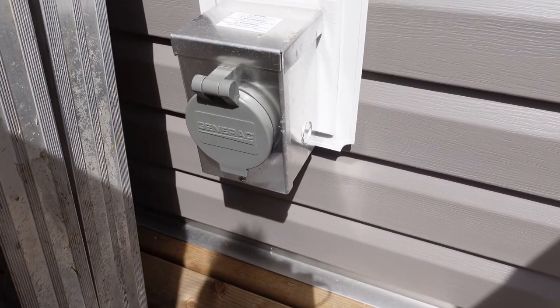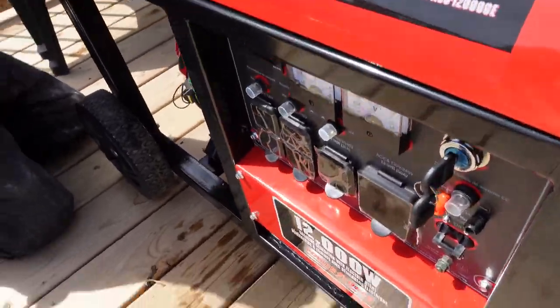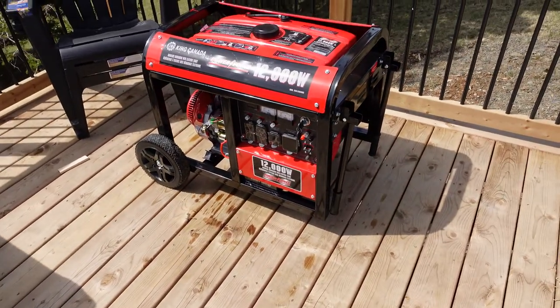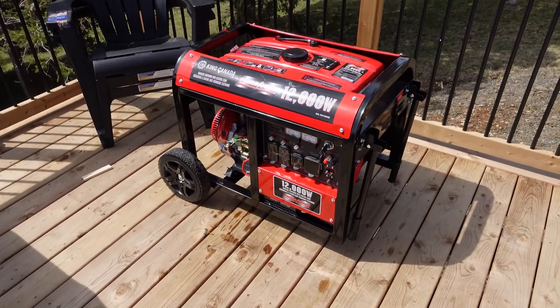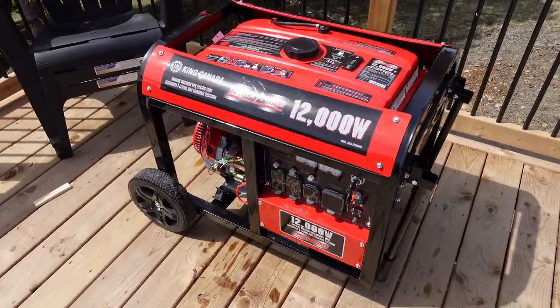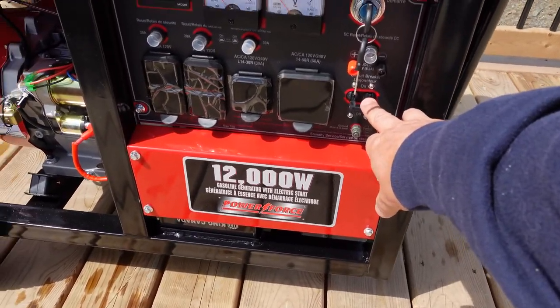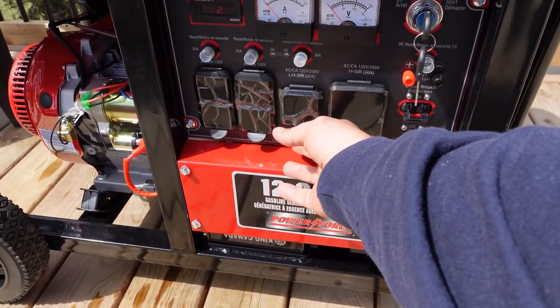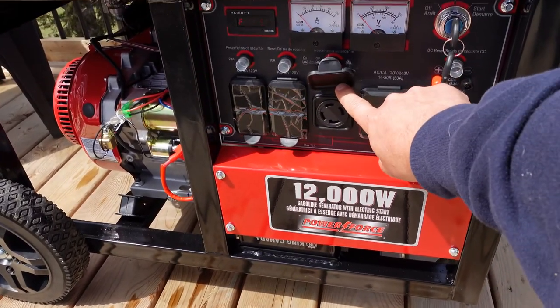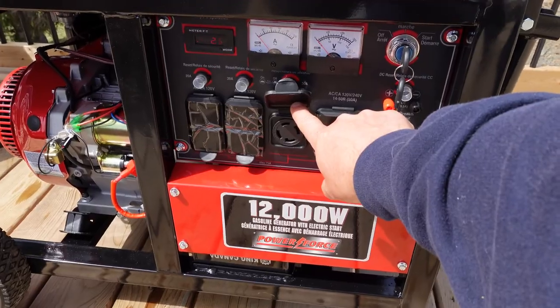Now we're going to do a startup and get the generator going. The first thing you're going to do is get your generator running. All models are a little different — some have a choke, some have electric start. On the side of the generator when you turn it on, you're going to want the breaker in the off position. This is the L14-30R receptacle that you're going to use, and this is where we're going to plug the plug into. Once the generator is warmed up you can go ahead and plug that in.